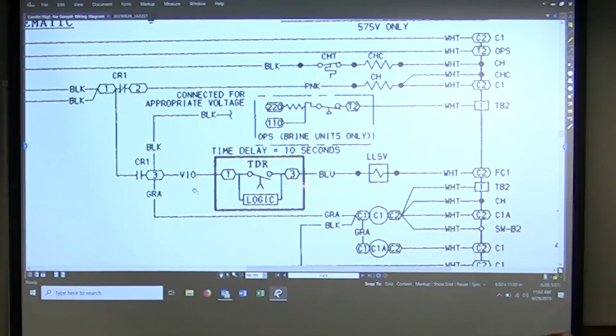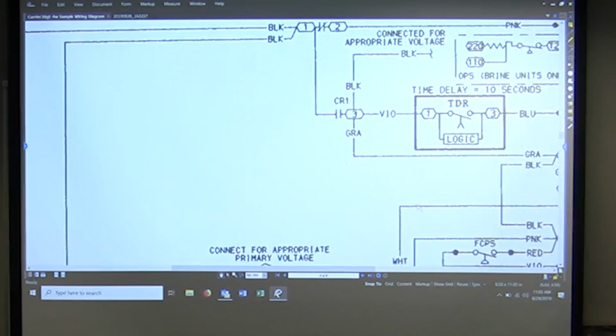Okay, what do I do here? It just goes through a time delay, so it says 10 seconds, and then energizes the liquid line solenoid. Okay, almost just set up on a pump down basis. Yeah, so when that shuts, the system pumps down, I get a low pressure, it turns things off, and it just stays there as long as I've got a low pressure. As soon as I open this, the pressures go back into normal operation mode. I'm no longer at low pressure; the low pressure switch makes, then closes and starts your compressor. The system is set up to keep the refrigerant out of the compressor, right? That's the whole concept.